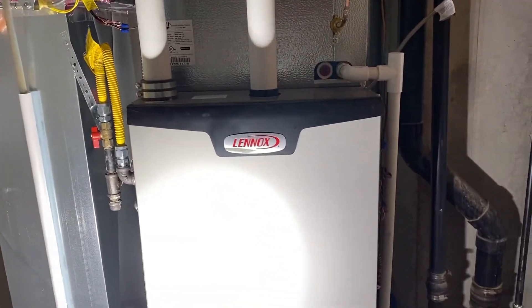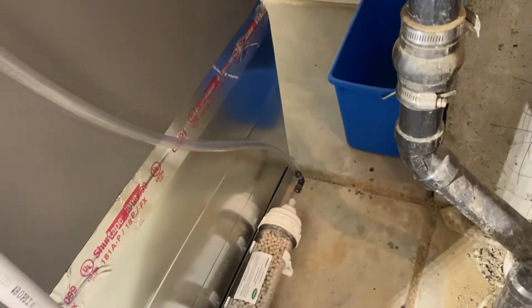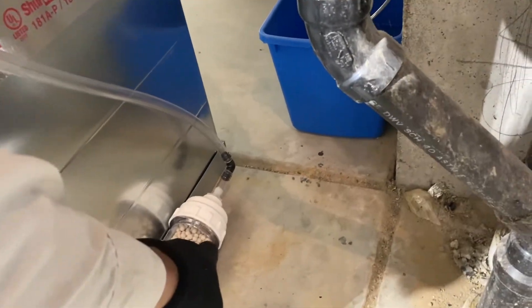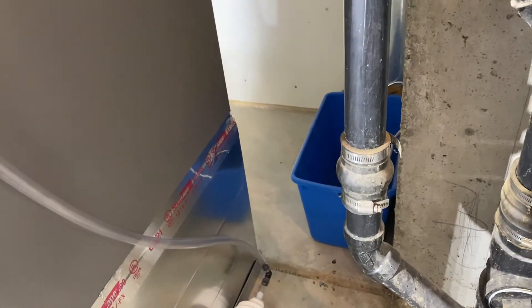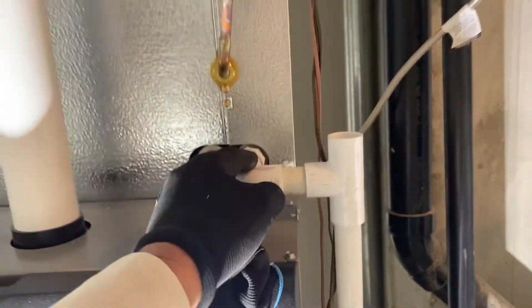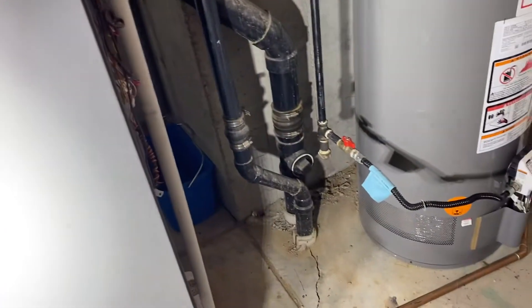This is the 96 percenter. I'm using an acid neutralizer — it is filled with water. You can see the discoloration back there but it's never been used, so it's not dirty. Using that as our P-trap like we always do. There's our connection drain for the AC coming over into here.